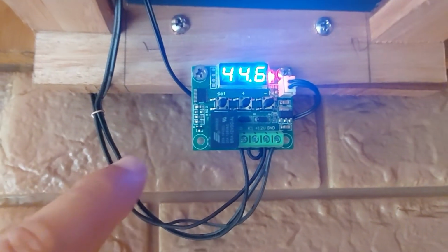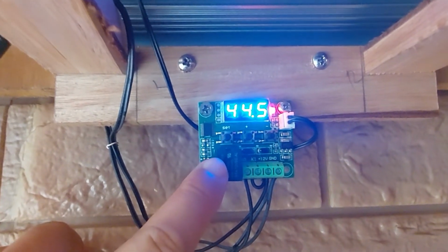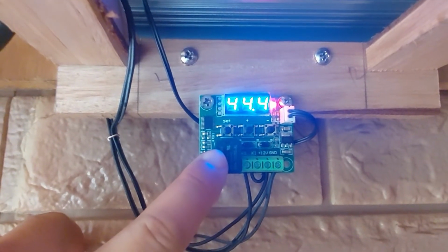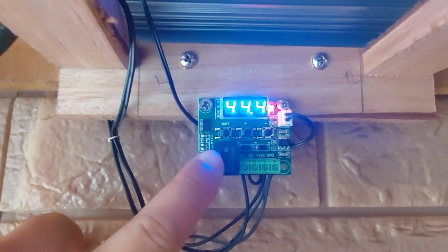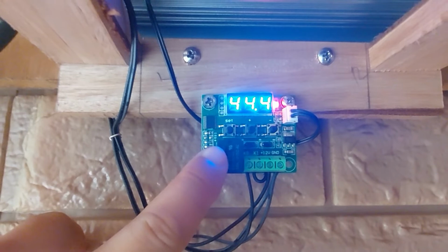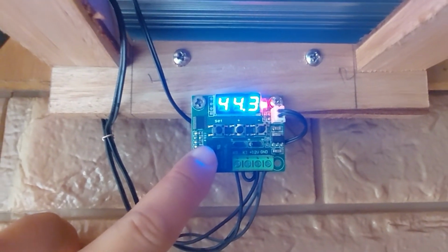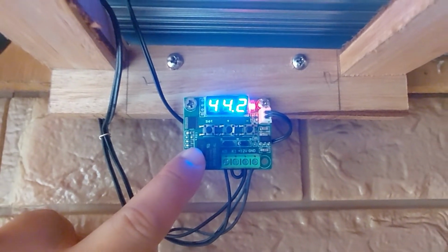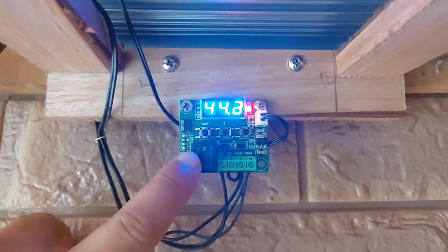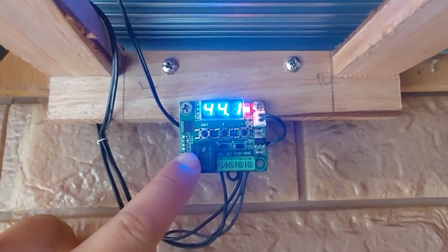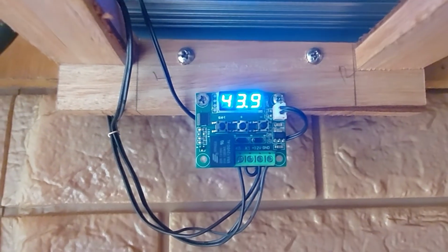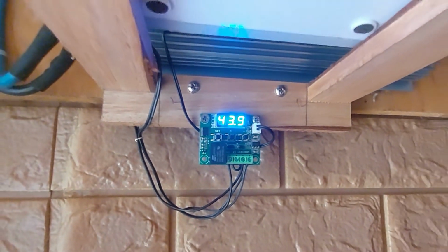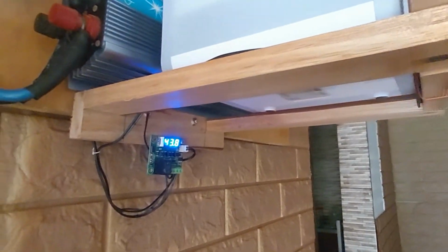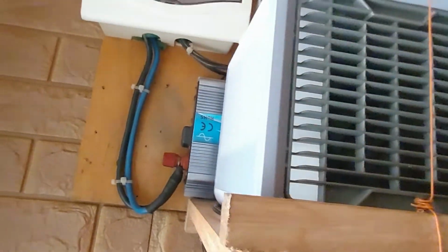By the way, you can manually set the return difference temperature of this one, since this is really a programmable temperature switch. So as the temperature goes down, it should cut off at 44 degrees. Just like that. So this is how the system is set up.